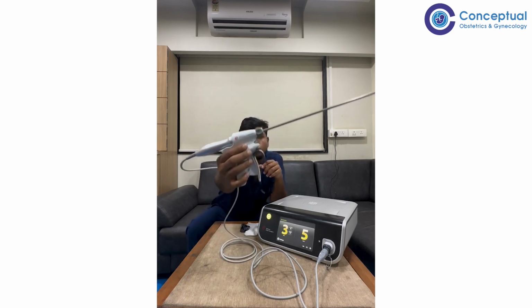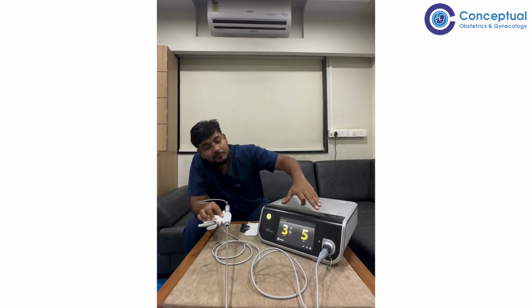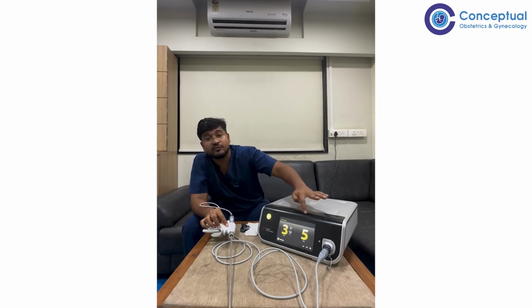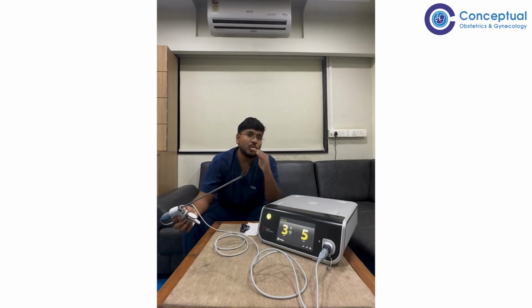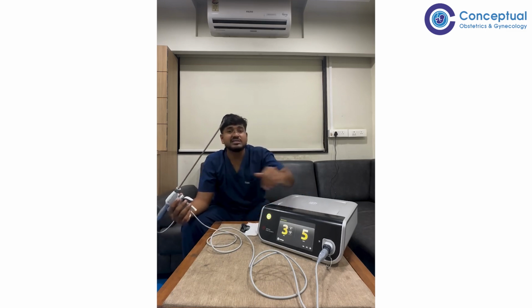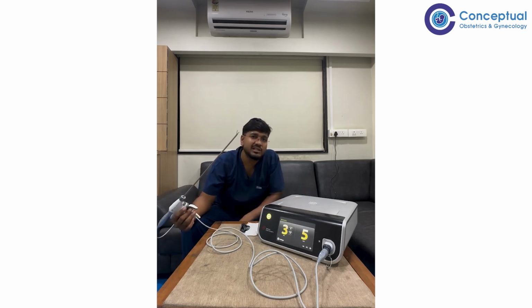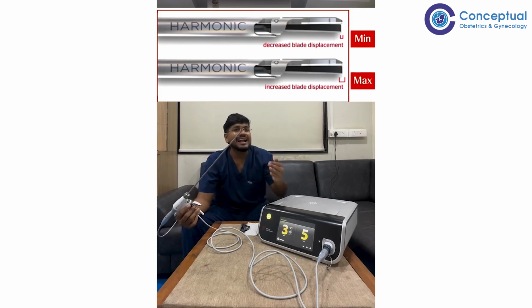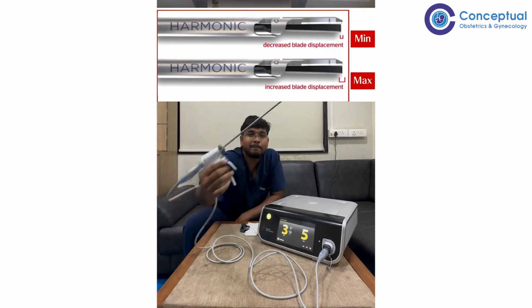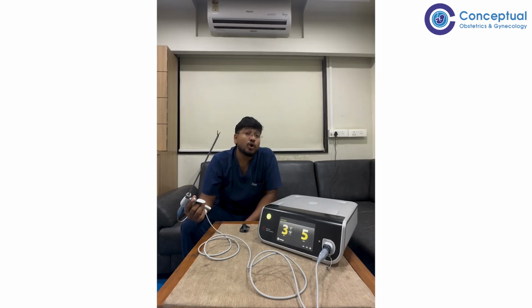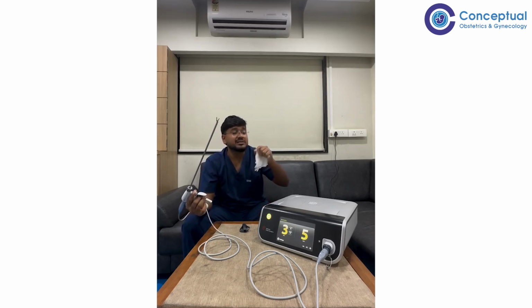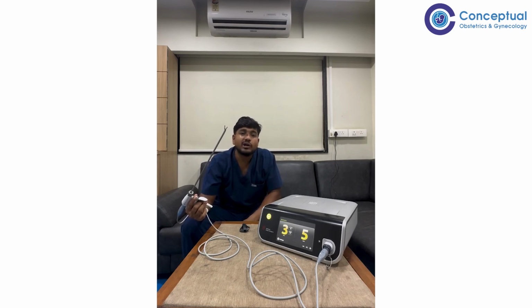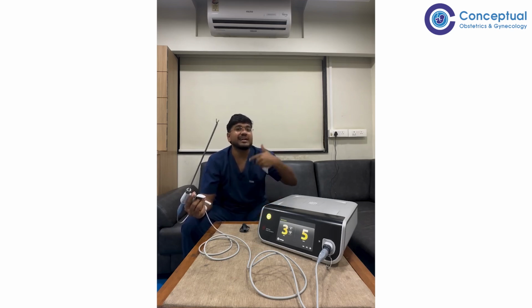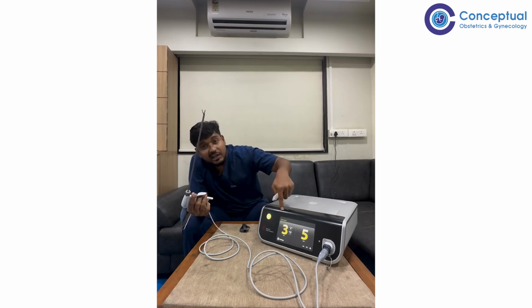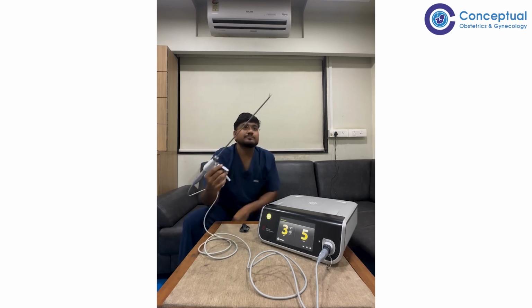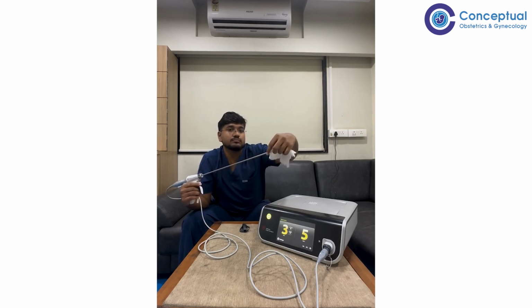Here if you see, you have two modes, maximum and minimum. On the system also you can see that there are two numbers, 3 and 5. So what does this mean? You have 5 levels, 1, 2, 3, 4, 5. Maximum current, when the level is at 5, this is vibrating at 55,000 cycles per second and the displacement is greater. At 3, 2 or 1, you use something called minimum. So when I use this for coagulation, I don't want it to be vibrating at high speeds, therefore transferring a larger energy. I want it to slowly hit the tissue in order to get the effect of coagulation. So I set it at 3 or 2 and then I press the minimum button and then I place it over the tissue.